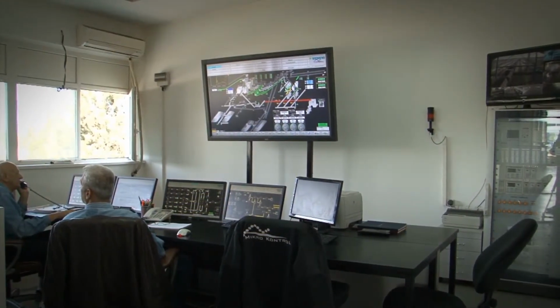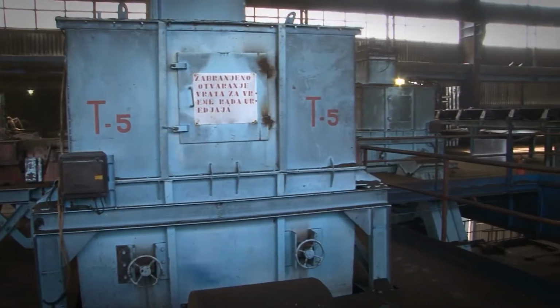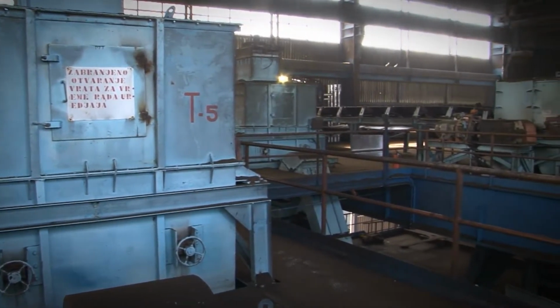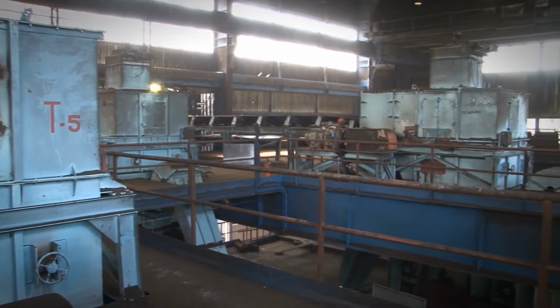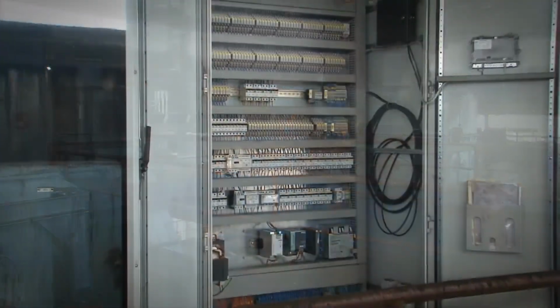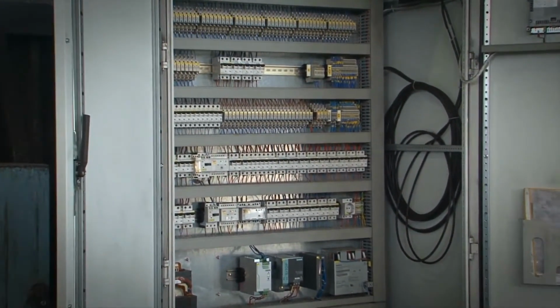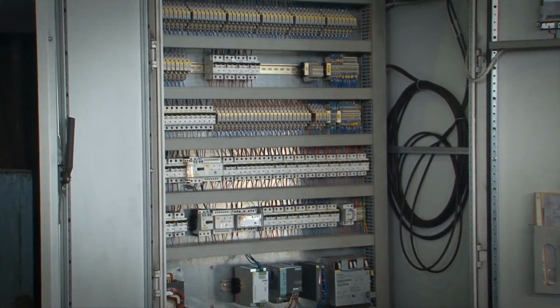As the process does not tolerate delays in production, redundancy was performed at the level of PLC stations, at the level of the Profibus DP network processors and network, and at the level of the operator SCADA stations.